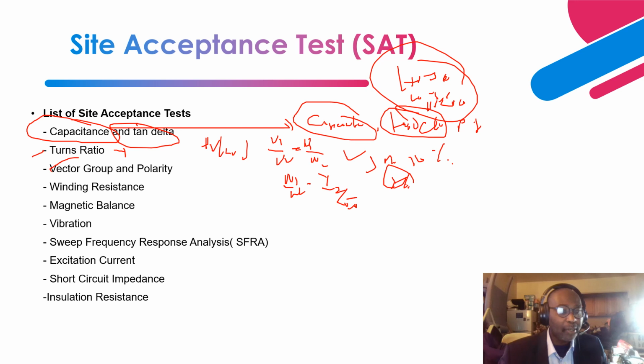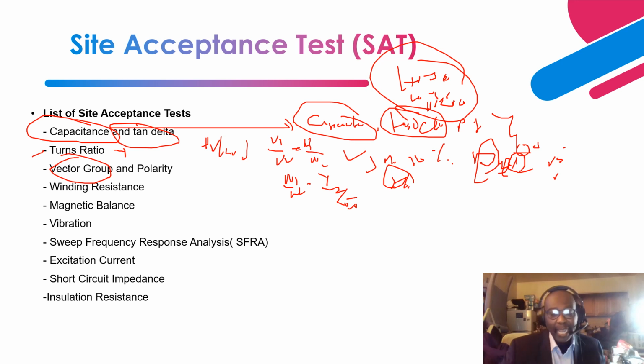Next is vector group, right? When we do the turns ratio, we also determine the vector group. The vector group, let's say for a DYN1 transformer: you have the high voltage wound in a delta configuration, and the low voltage wound in a Y ground configuration, right? And the grounding could either be solidly grounded, resistance grounded, or reactor grounded. And the number shows the phase shift between the high voltage side and the low voltage side. So here we have a 1. That means that the high voltage side leads the low voltage side by 30 degrees.